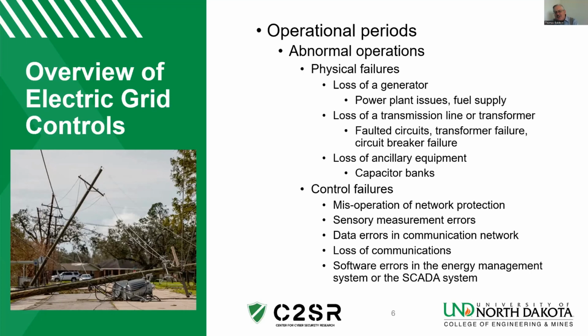State estimation, if done correctly, should be able to identify bad pieces of information, flag that, and remove extreme pieces of data errors. On the other hand, it can help reduce the sensitivity to normal measurement errors that always take place in equipment as calibration drifts over time. State estimation has had the challenge that it has been static in nature and taken samplings on the order of 15 minutes to maybe even 30 minutes, so it only gives you a snapshot of the system. But that's changing as resources in communication sensors, as well as software and computing systems, have improved.